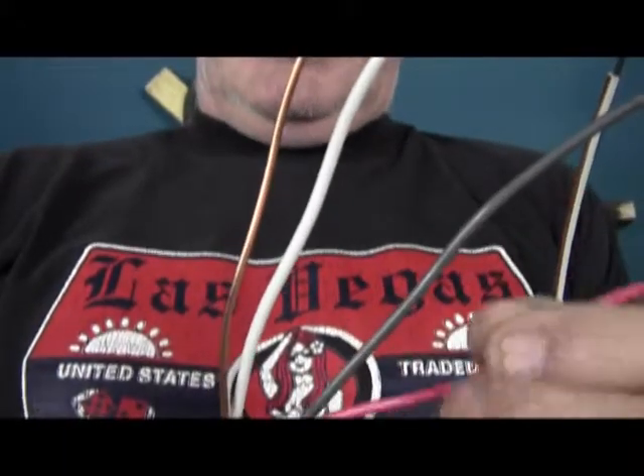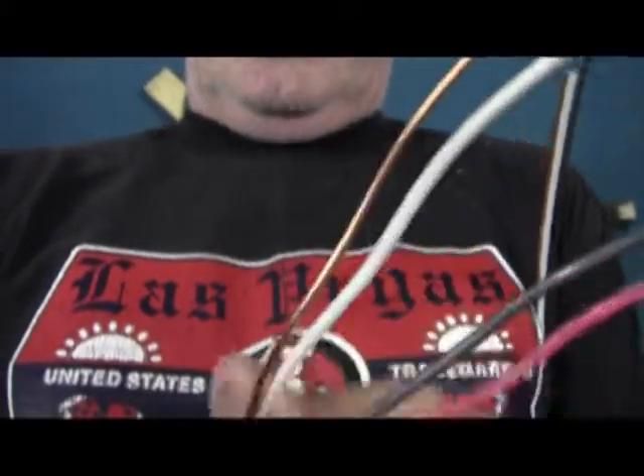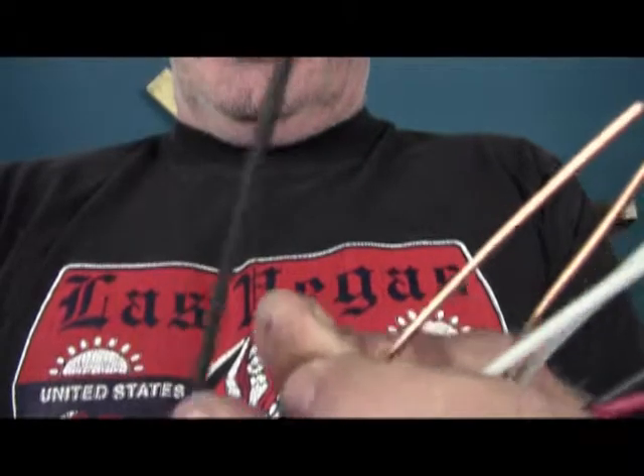This differs from 12-2, which does not have a red. It simply has a white, a ground, and a black. Now on a three-way switch, the 12-3 is used as your travelers.